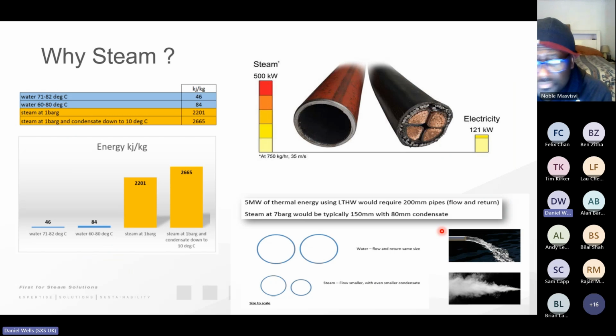So we know that for many processors, it may be absolutely the right thing to do for those thermal energy processors to transition from steam to an alternative, such as low temperature hot water. For example, low temperature hot water that could be produced by a heat pump. And like I said, in many cases, that's going to be not only attractive and the right thing to do, but if we transition from a steam system to a water-based system without giving it due thought and consideration, we could experience a significant number of issues and problems.